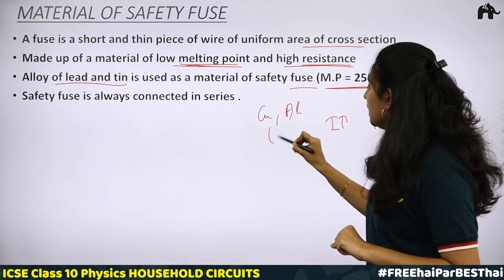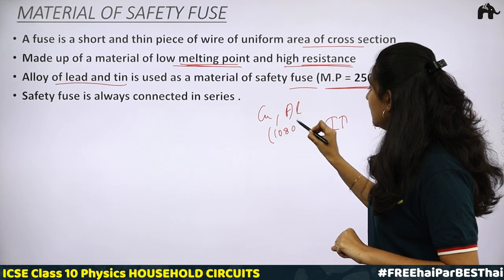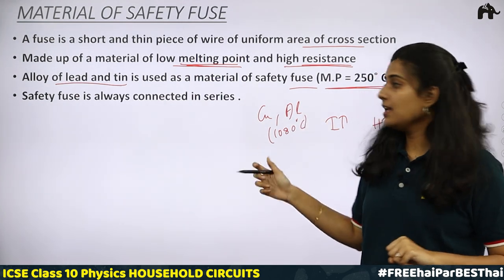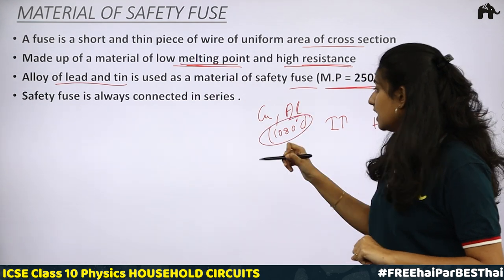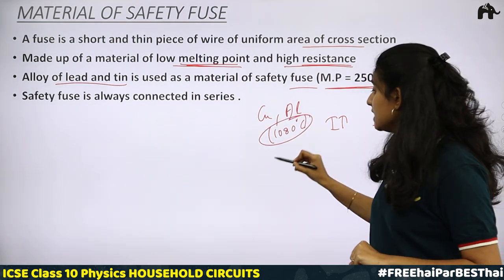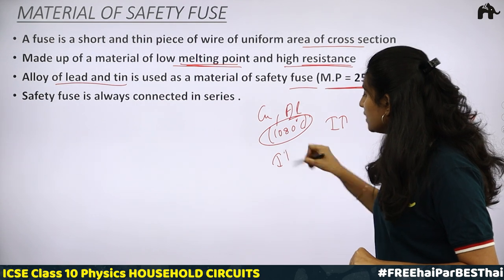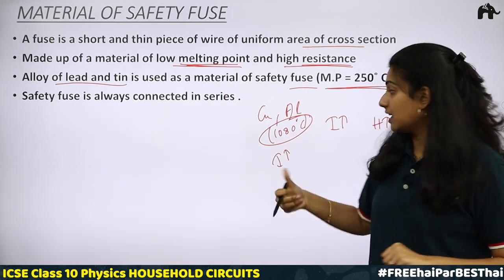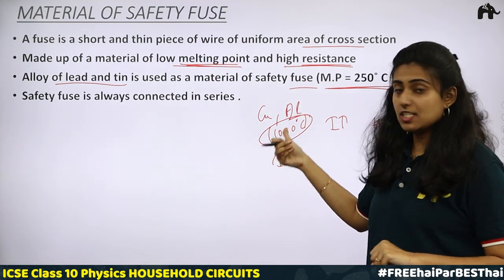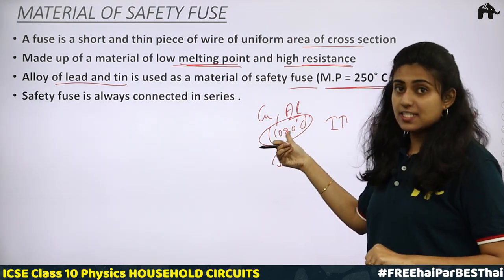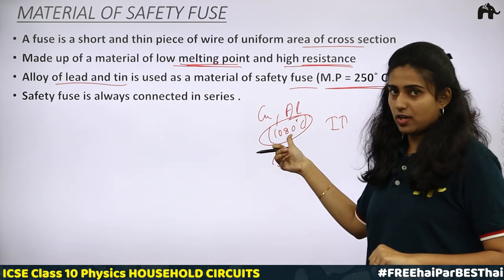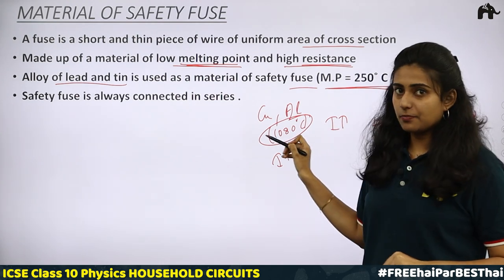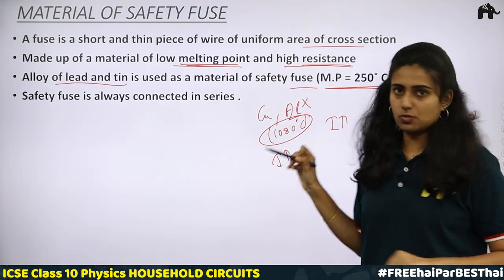If you use copper or aluminum, in these cases the melting point is about 1080 degrees Celsius. Can it be used for making a fuse? No, because the melting point is high — so much current must be given to reach that temperature, making it difficult. So these materials cannot be used for making a safety fuse.